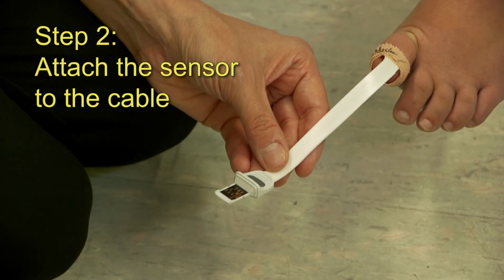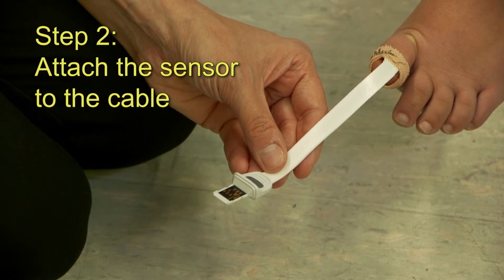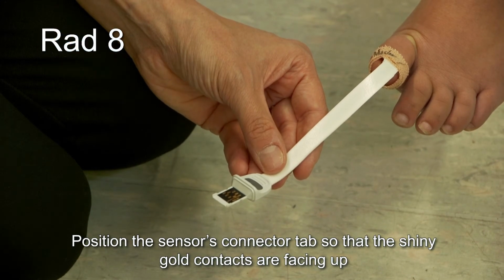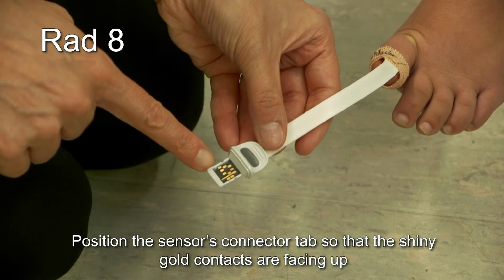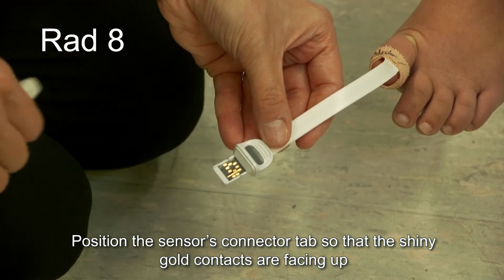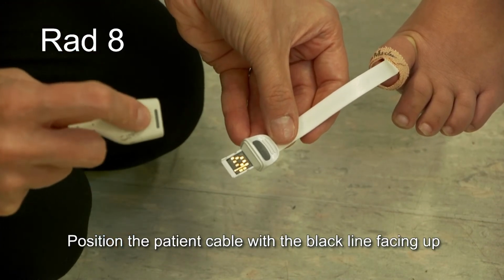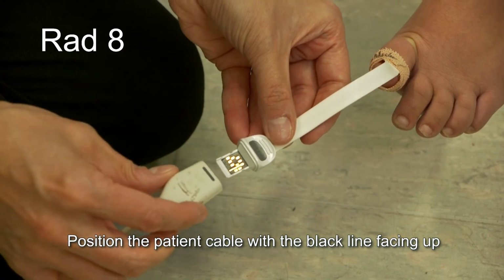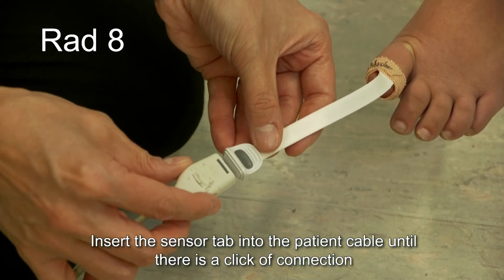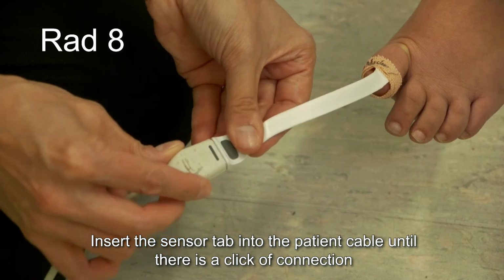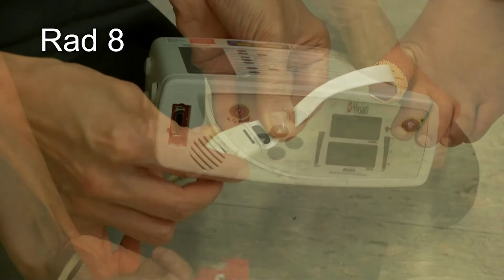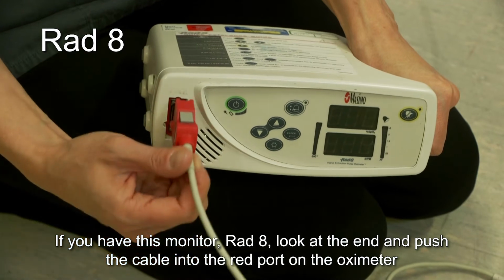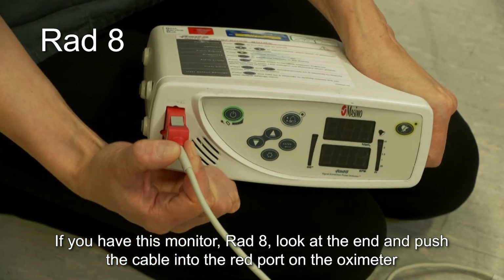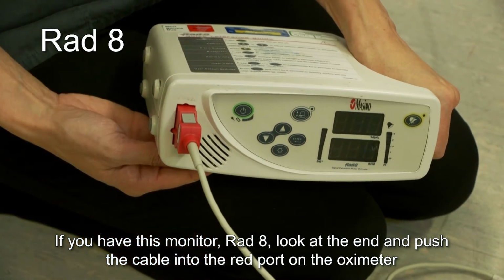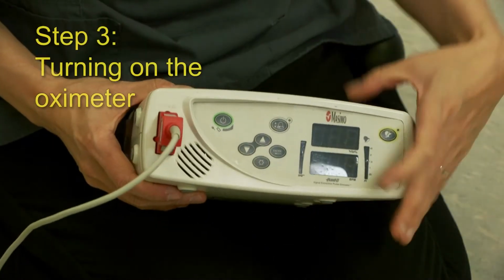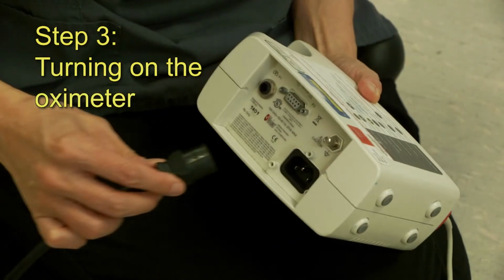Step 2. Attach the sensor to the cable. For the RAD8, position the sensor connector tab so that the shiny gold contacts are facing up. Position the patient cable with the black line facing up. Insert the sensor tab into the patient cable until there is a click of connection. If you have this monitor, RAD8, look at the end and push the cable into the red port on the oximeter.